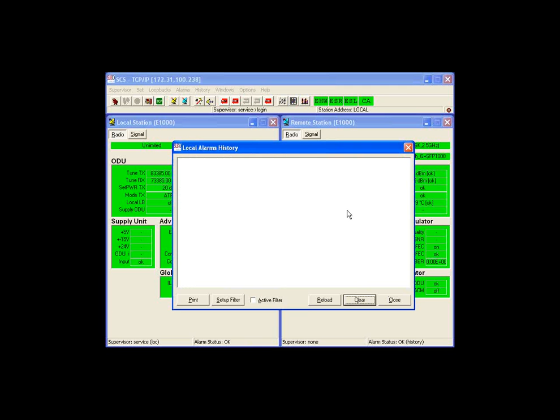Regarding the alarms, it's just mapping of how alarms are mapped. But for troubleshooting, the historical alarms or alarm history is useful. The system reads up to 600 events from the device: starting from 1 are the real first events, then around 256 or 300 are the first alarms, and from 303 till the end of the file the system puts the last 300 events. This is useful if you have a link running for a long time, so you don't lose the first and last data. Anytime you're troubleshooting and need fresh data, you can simply clear it, and it starts again from the startup.